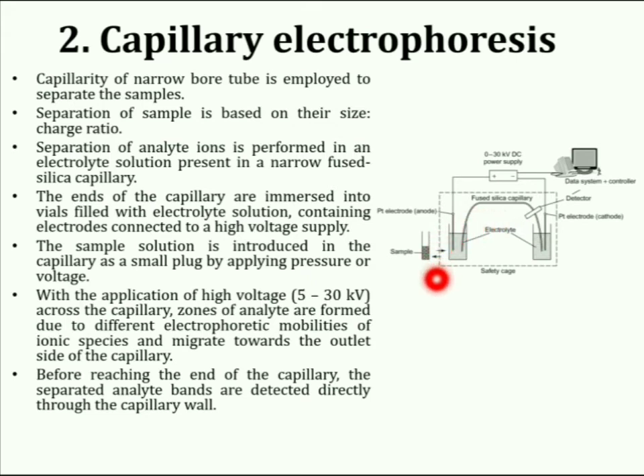The ends of the capillary are immersed into inlet and outlet vials filled with electrolyte solution. Inlet and outlet vials also contain electrodes connected to a high voltage supply. The sample solution is introduced into the capillary as a small plug by applying pressure through hydrodynamic injection or by voltage through electro-kinetic injection. Due to the high voltage across the capillary, zones of analyte are formed due to different electrophoretic mobilities of ionic species, which tend to migrate towards the outlet side of the capillary. Different ions can be separated when their charge-to-size ratio differs.